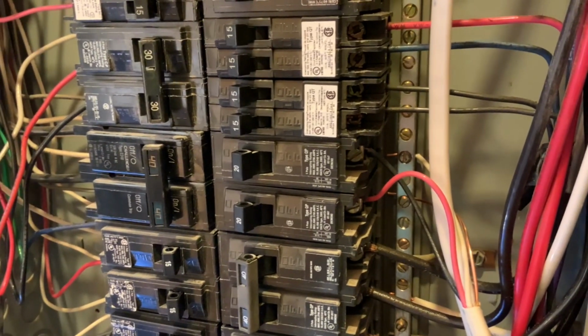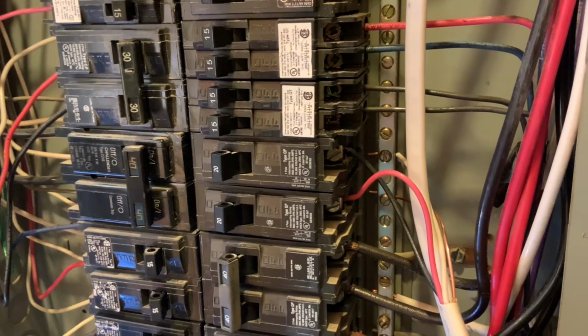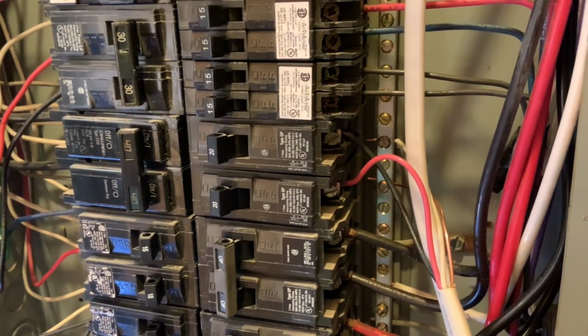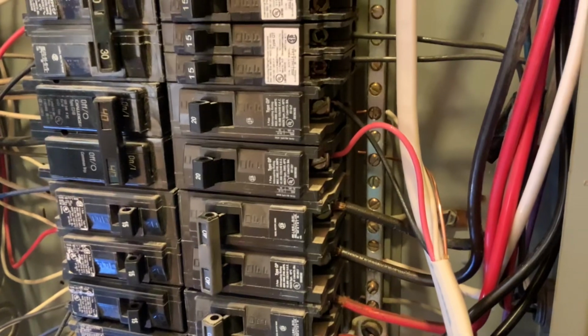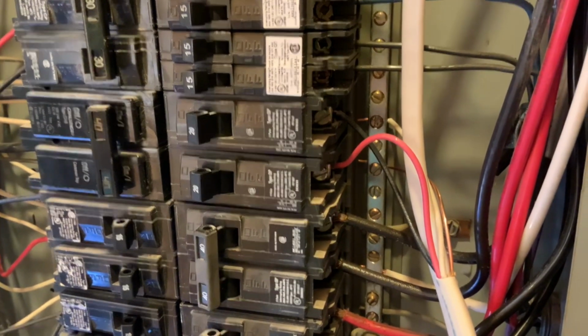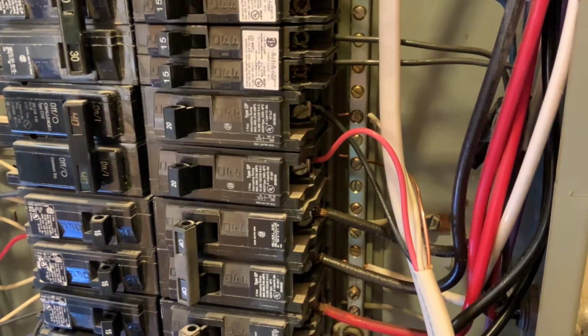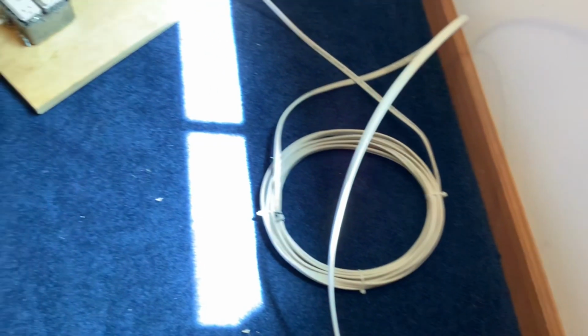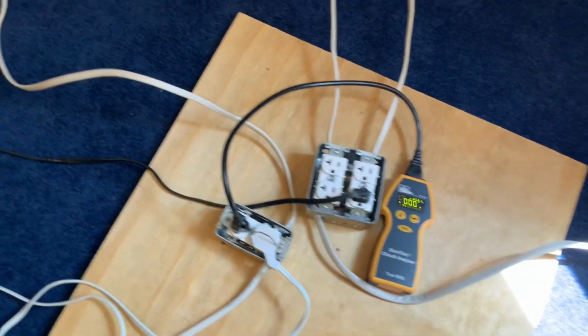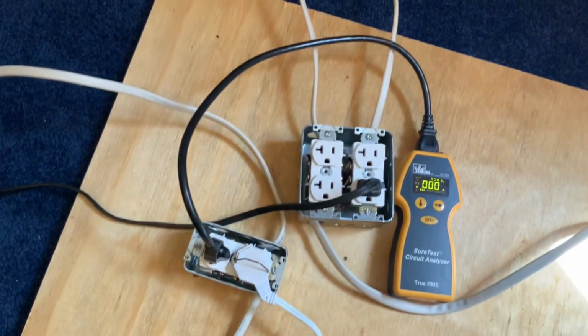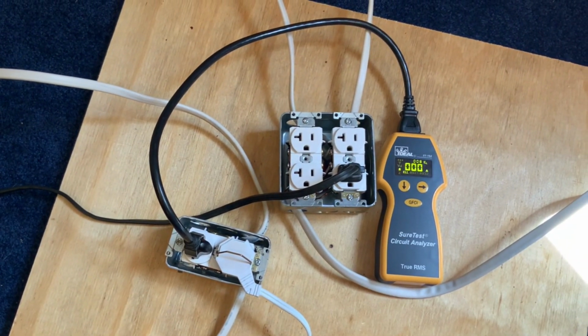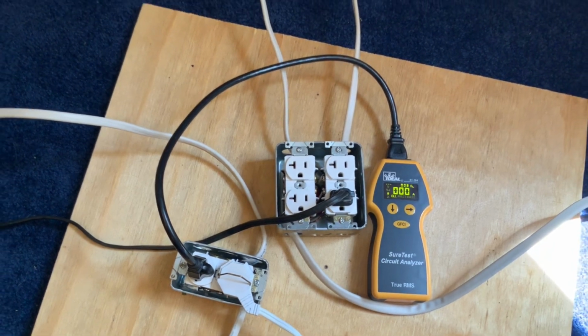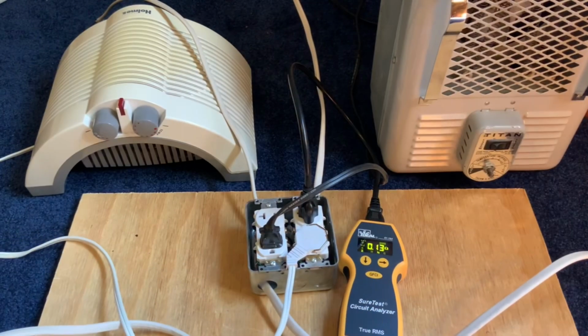So here's a balanced ground situation where we have two phases running in one piece of Romex. The black and red wire are each a phase and each have their own circuit breaker, but they share a ground wire. So I've taken these two wires and I've run them to two separate outlets. One outlet will have the one phase on it and the other outlet will have the other phase, but they share a ground wire. So what should happen here is when I have high current flowing from one of these outlets, the current flowing in the other outlet should cancel out that current and you don't have as much current actually flowing on the ground wire.